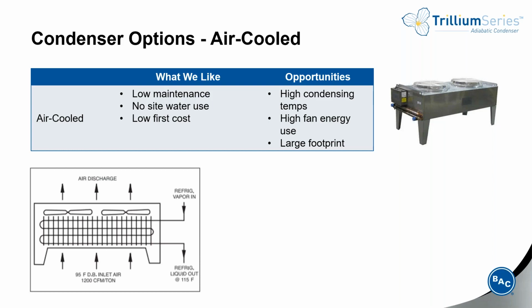Those high condensing temperatures mean larger compressors, more compressor energy. Typically, we also need a large volume of air for this heat exchange to happen. So that means high fan energy and high noise. And along those same lines, we need a lot of surface area on the coil to achieve this heat exchange. So large surface area on the coil means large footprint in our equipment.